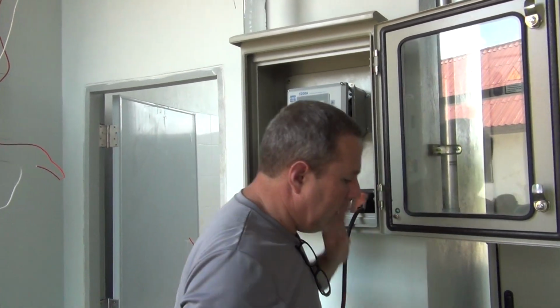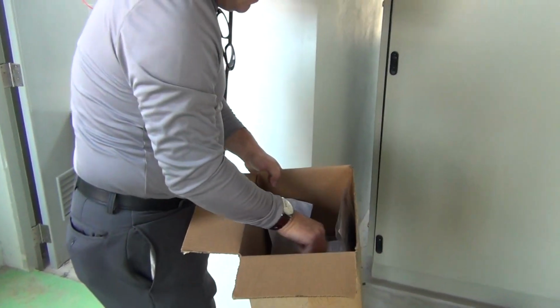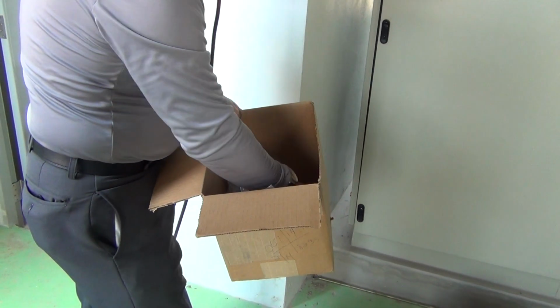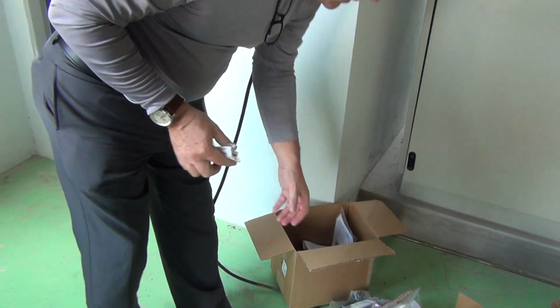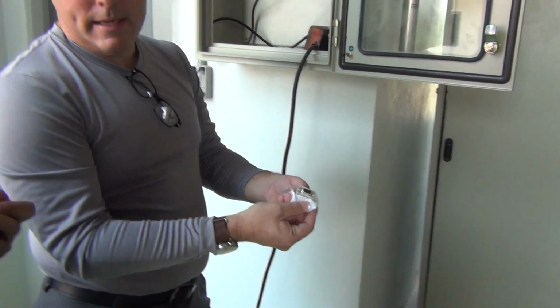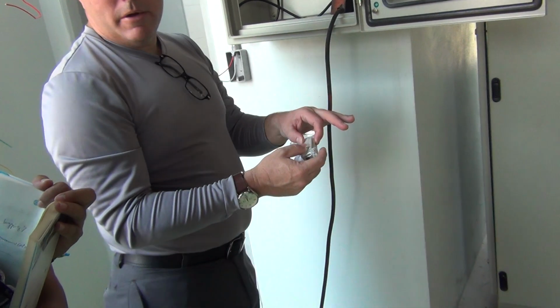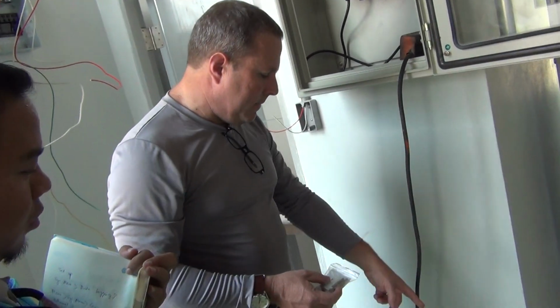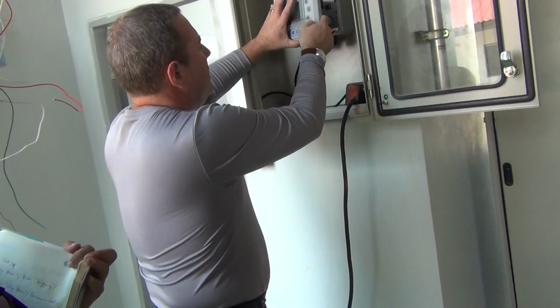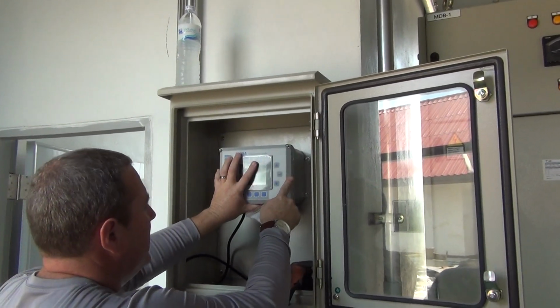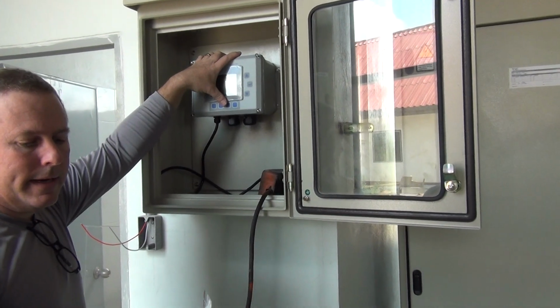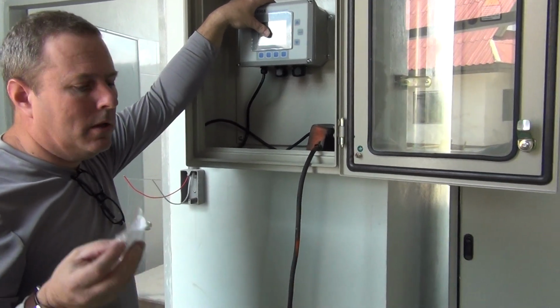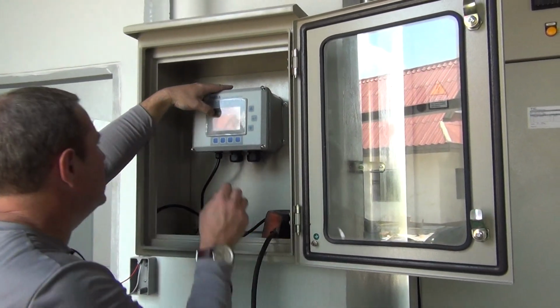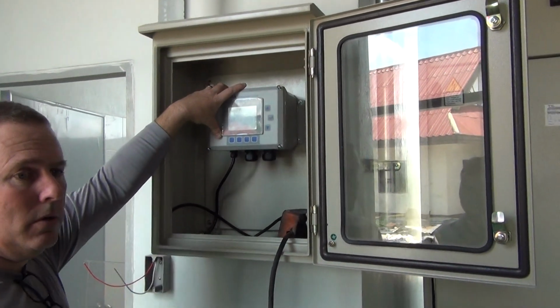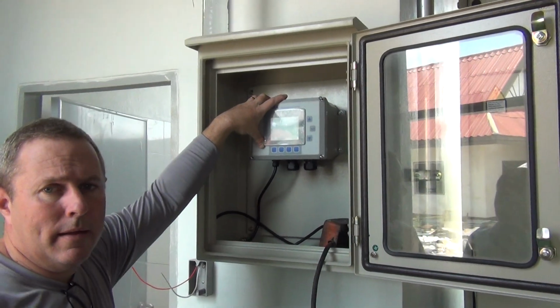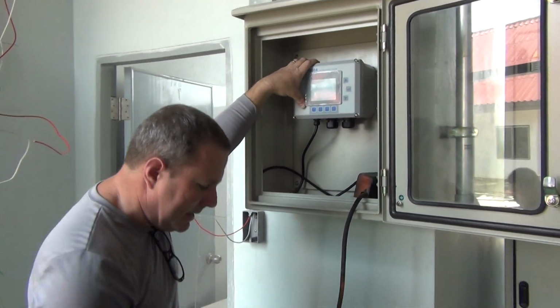Now, in the items that you've received should be, yes, this is an RJ45 to DB9 connector that is pre-wired as a null modem. So you would take the blue cable that came with it, the RJ45 cable, you would plug that into the serial input. You would take the other end and plug it into here, and then connect this into your serial port. And it could be a USB to serial or a serial port on a computer. And then you would use the downloader, and you would press that, and when you do, it goes into a mode that it's ready to receive the data from the Aqua Manager software, which is that CD.